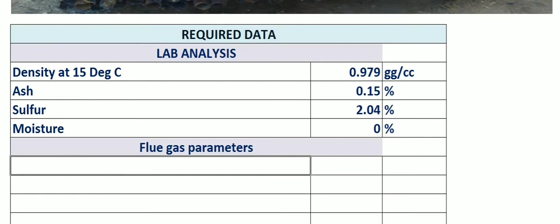Actually, we are going to calculate the sulfur dioxide dew point. So we need to find out how much sulfur dioxide is generated in the boiler or furnace and exits through the stack, and how much water vapor H2O is formed. We need both of these. So we want to do the stoichiometric calculations, that is the air required for complete combustion. By this we can calculate the other components also. So O2 in flue gas, just before the stack entry, in our case is 7.5%. These are all weight by weight.